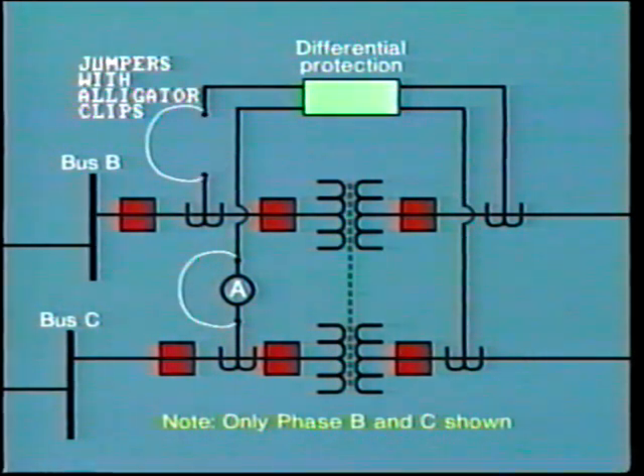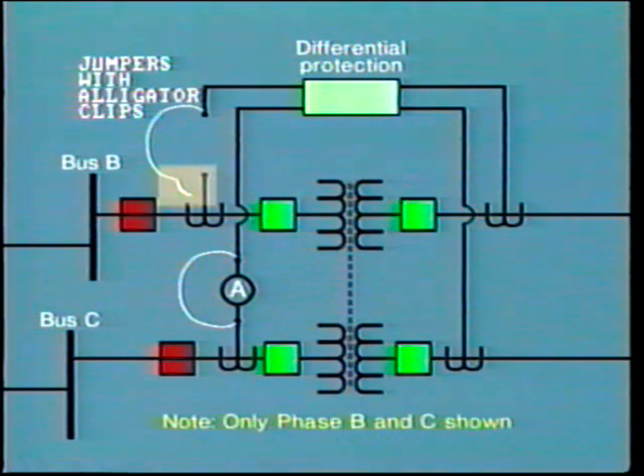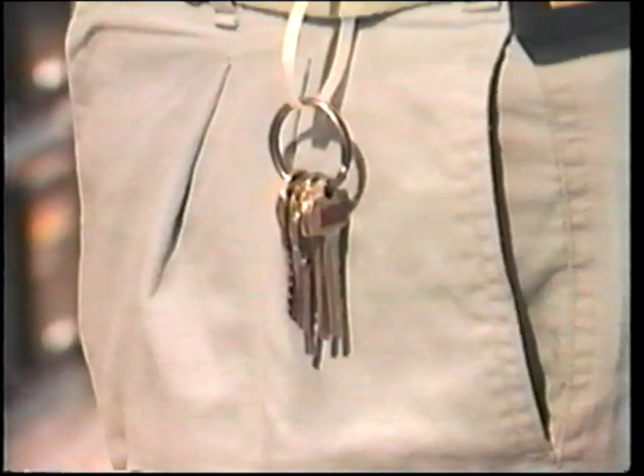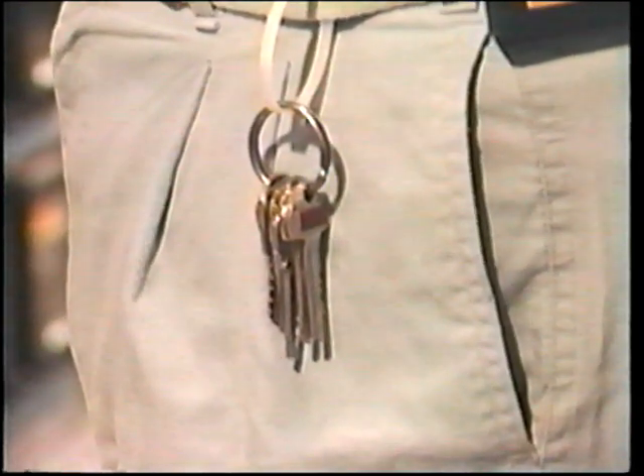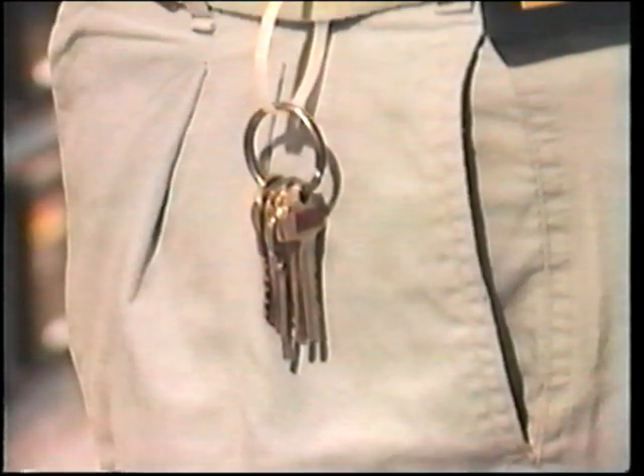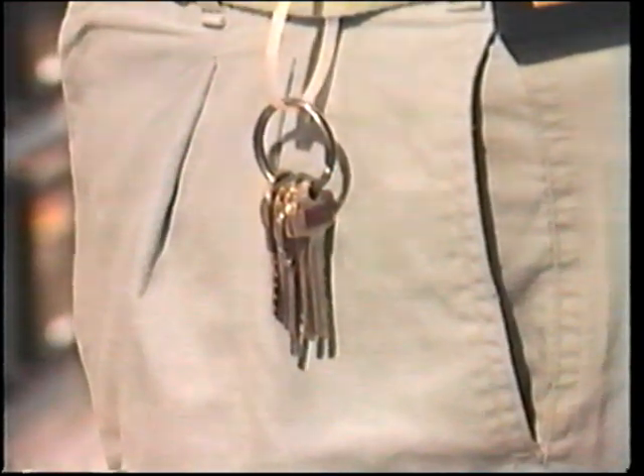As soon as the work commenced, the transformer tripped on differential. It appears likely that one of the alligator clips became disconnected, and so energized the differential protection circuit. There is another possibility. It was noticed that one of the technicians was wearing a large bunch of keys on his belt. Perhaps these keys bridged contacts on the CT terminal block.